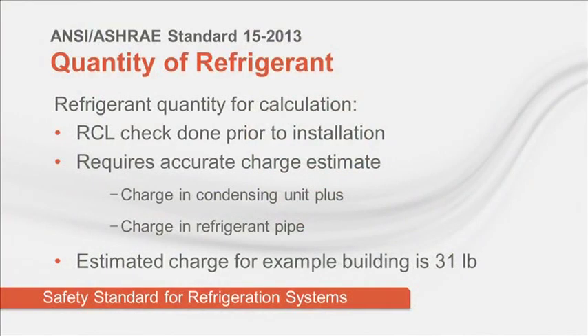For our example building, all of the indoor units are served by a single circuit. Total charge is the refrigerant charge shipped in the condensing unit, plus any additional charge added on site for refrigerant lines. Because the Standard 15 analysis is done before the system is installed, a detailed layout of refrigerant piping must be made in order to facilitate an accurate total charge estimate. For our example system, the total charge estimate is 31 pounds. The next step is to calculate dilution volume.